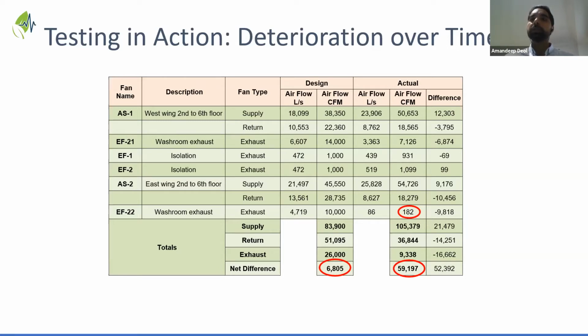There have always been issues like that, but I think what this example shows is that fundamentally, if you have issues in the building, it's just going to drive you to the air testing systems, especially around pressurization. And you're going to see that once the air testing results come, there is a story hidden in it. In this case, it's pretty clear that the system is not performing as expected compared with the design. And the result of this will be big energy savings in fan power and heating and cooling and humidification, in all of the above. Exactly, yeah.